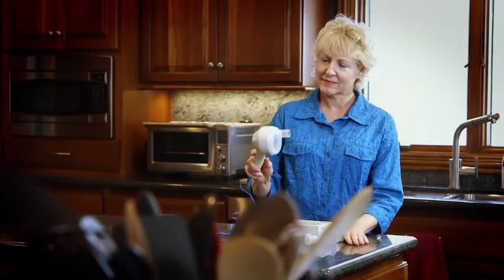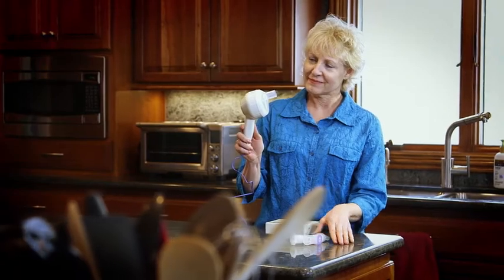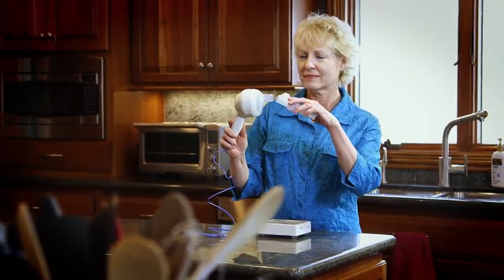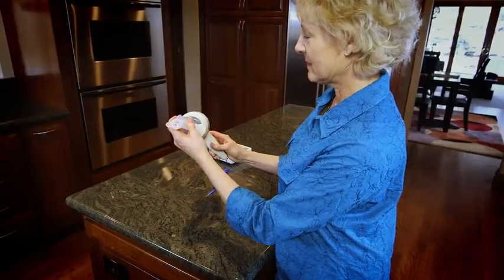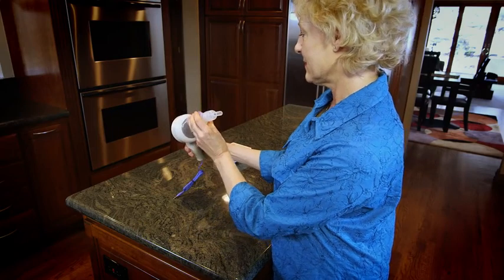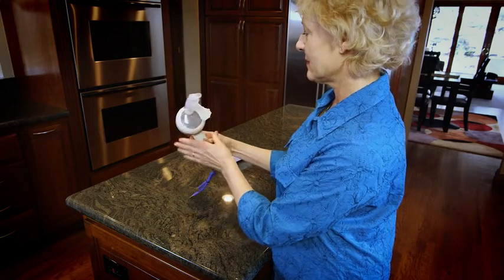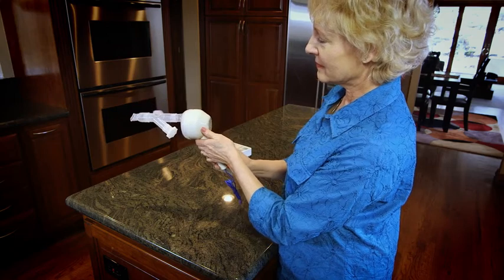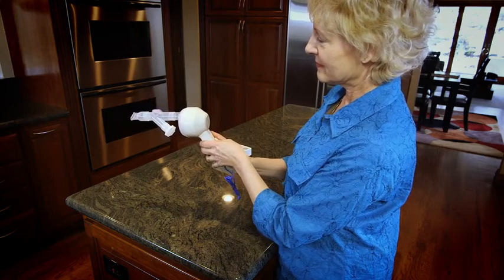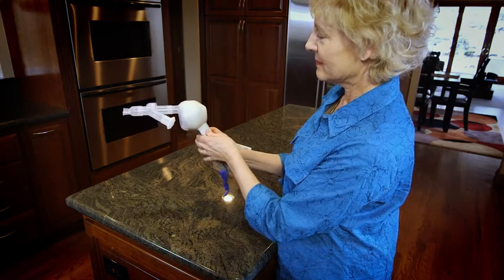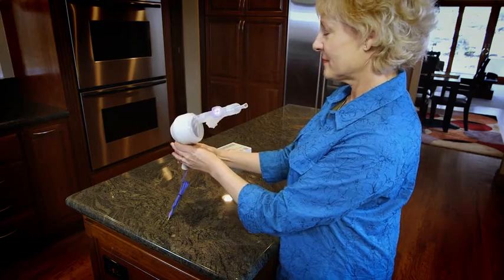Now assemble the Vibralung handheld transducer. Connect the long end of the standard Y adapter to the cone. The mouthpiece should be at the other end, and the variable expiratory resistor should be on the tail of the Y. The outlet port of the cone should be at the 3 o'clock position as you are facing it, and the assembly should be aligned as shown.